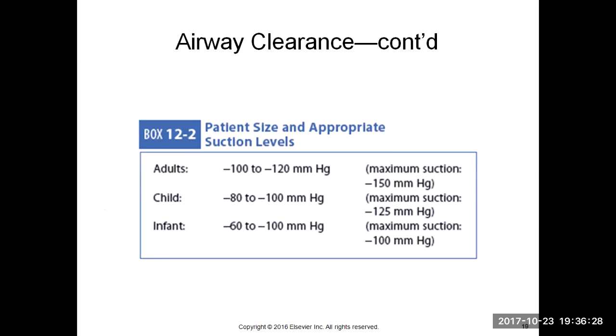So suction levels: 100, 120 or higher with adults, maximum of 150. Child 80 to 100, and infant 60 to 100. And our NICU kids, we run our suction at 80, which is usually our protocol. Kids around 80 to 100, like it says there, and we usually run adults around 140 in the unit I work in. We don't want to run too high because your suction device can attach itself to your airway.